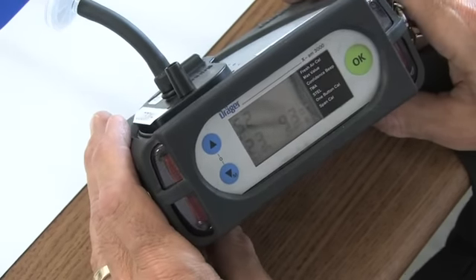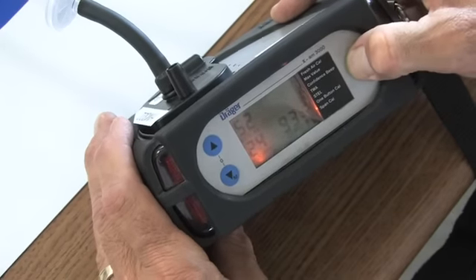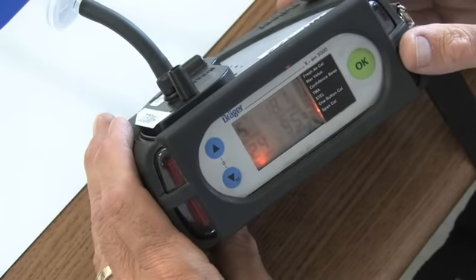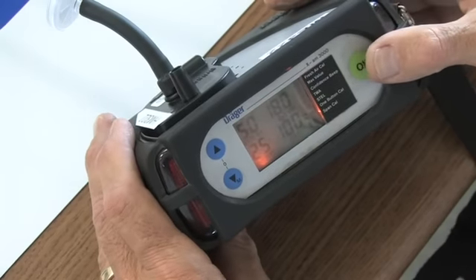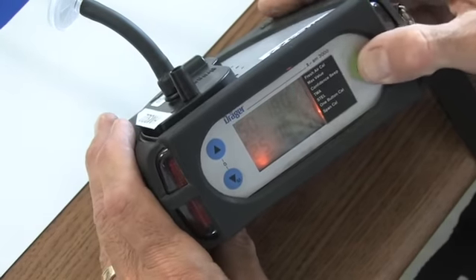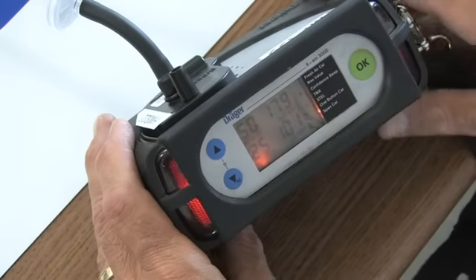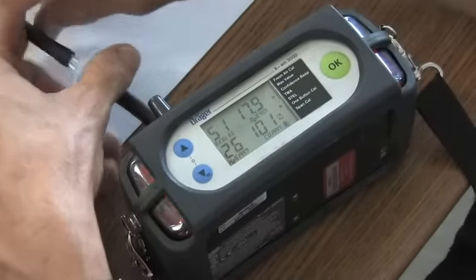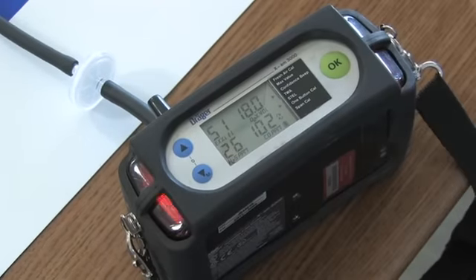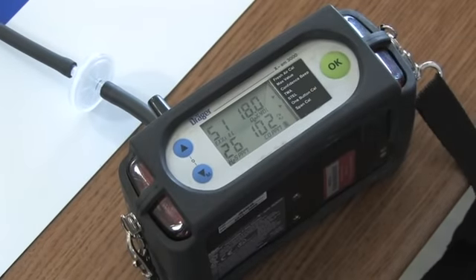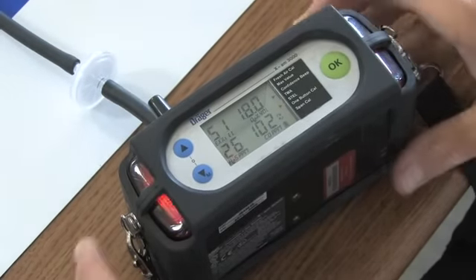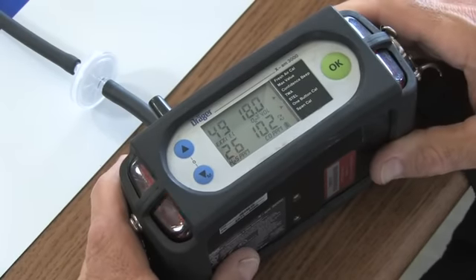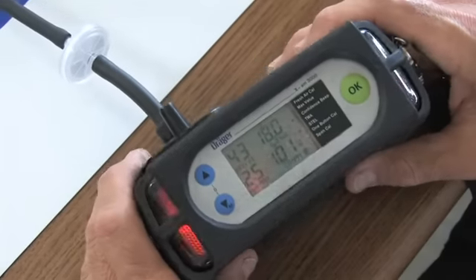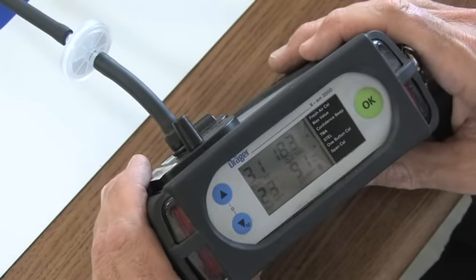We've been rolling for about a minute. So I'm going to go ahead and push the OK button. And there's my OK. Oxygen now comes back into the loop, although I'm really not part of it. And the calibration is over. And now we're reading our measurement menu, our instantaneous screen, and then we disconnect from the demand flow regulator. And again, this instrument has a tactile alarm, ever so slight, but it does have a tactile alarm to it. And then we'll wait for this to clear.